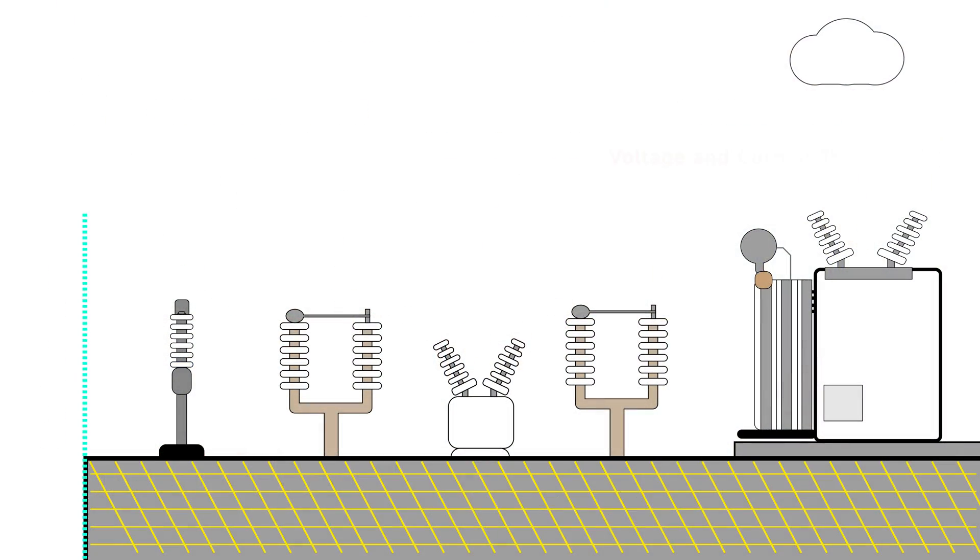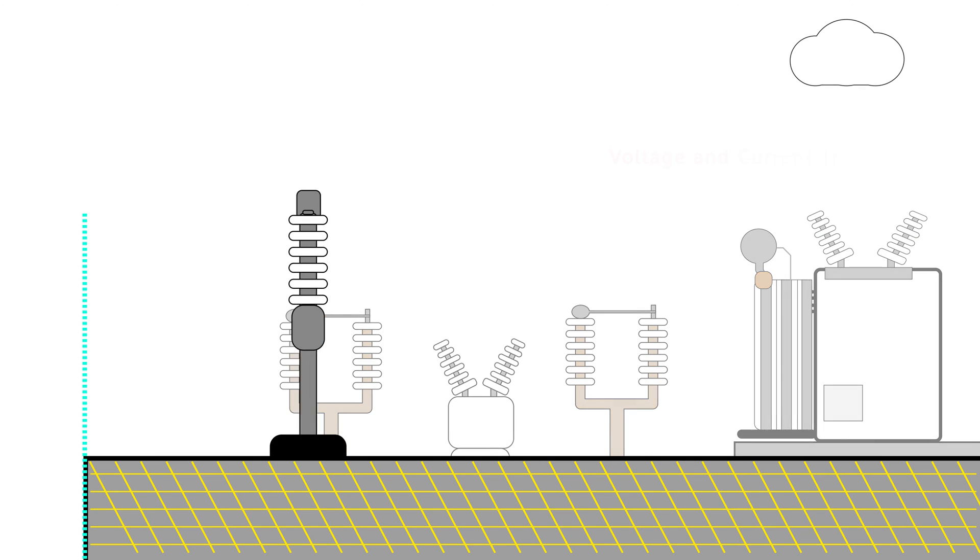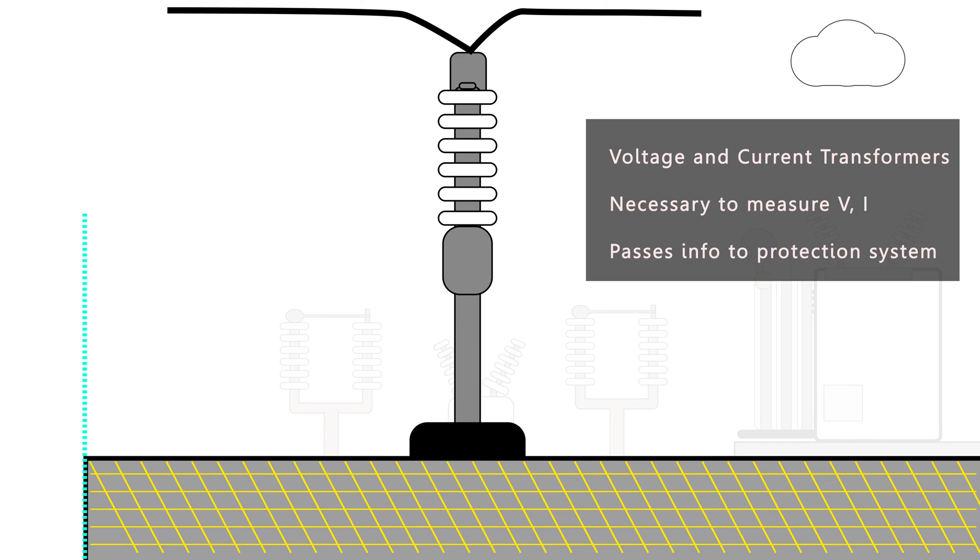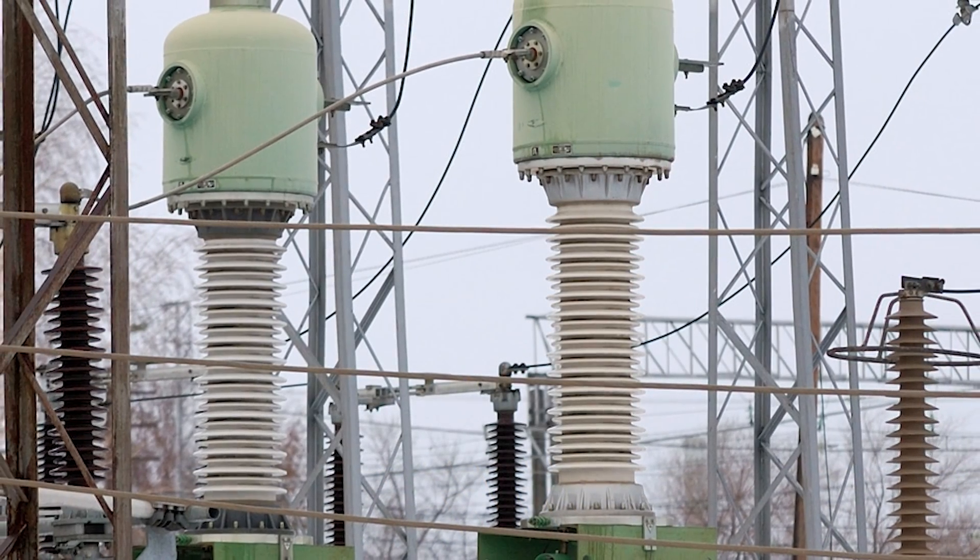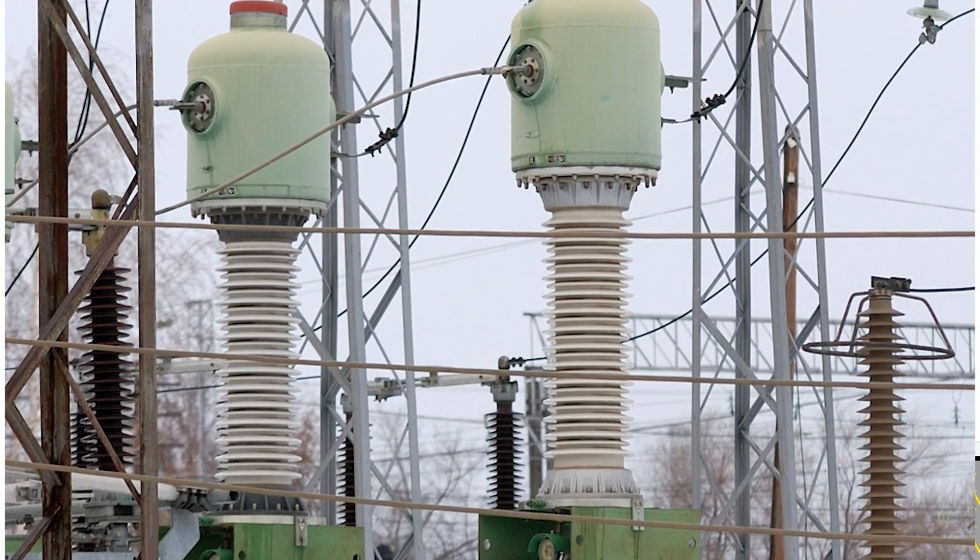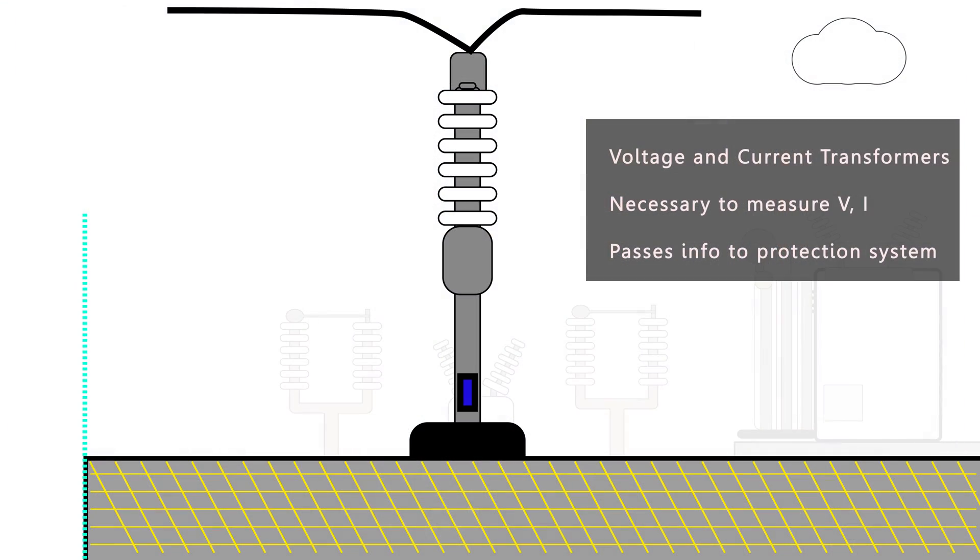Now the first asset we'll look at is the voltage transformer or current transformer. Normally a substation has both. VTs and CTs have the job of measuring voltage and current in the substation. It then passes this information either directly to a relay to make the decision on whether a fault condition is present, or it goes into the communication infrastructure of the substation and then is passed on to the control room.